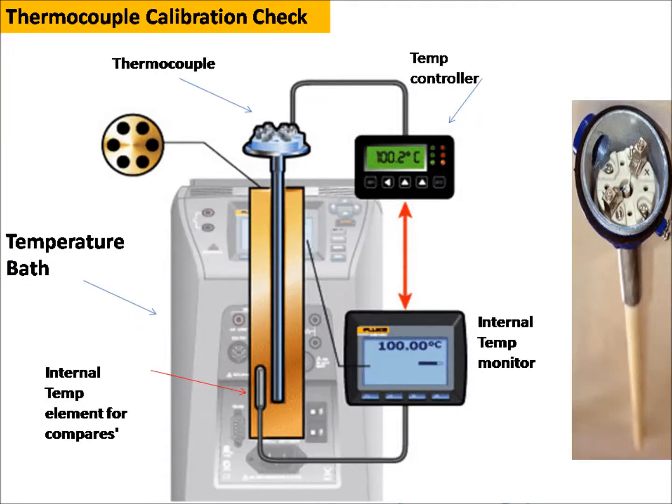Suppose you want to check a thermocouple at 100 degrees Celsius. First, insert the thermocouple inside the bath and set the temperature to 100°C. Wait until the temperature is stable at 100°C. Then set 150°C and check it. This way you can check with 50-degree temperature graduations, and then decrease in the same manner step by step.